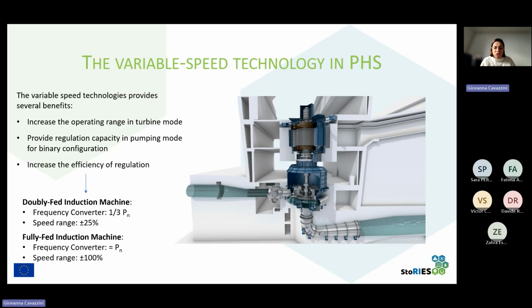But a second option has also been introduced recently, which is the fully fed induction electrical machine. These machines are equipped with a full-size frequency converter, and this has enabled the possibility of varying the speed in an extremely wide range, of plus or minus 100%. So there is the full possibility of completely varying the speed from 0 to 100%. Of course, this comes at a price. Fully fed machines are much more expensive in comparison with doubly fed, and depending on the needs of the power plant during the design phase, it can be foreseen to use one option or the other.